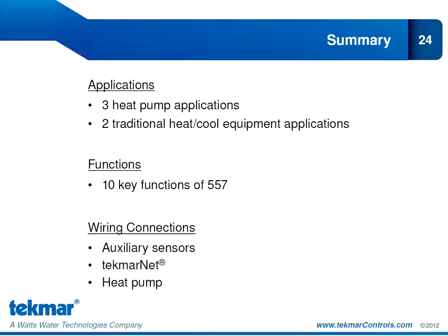To summarize, we covered those 3 heat pump applications that the 557 was designed for. We also covered 2 traditional heat-cool equipment applications to reinforce that the 557 is not just a heat pump thermostat. We went over the 10 key functions of the 557, including the radiant floor warm weather shutdown, balance point schedule, and relative humidity measurement and control. We also went over the wiring connections. So we looked at the 3 auxiliary sensor input terminals. We looked at the tekmarNet connections. It can be tekmarNet 2, tekmarNet 4, or standalone. And we looked at how simple the connections are to the heat pump.